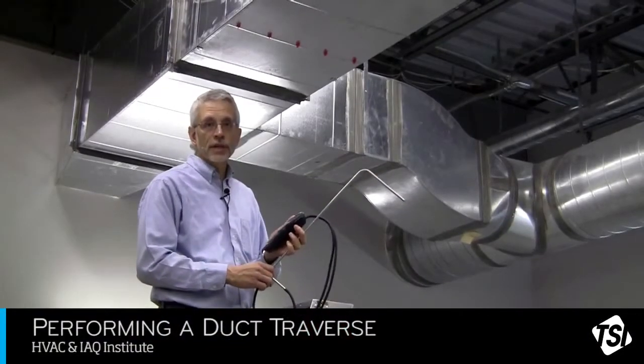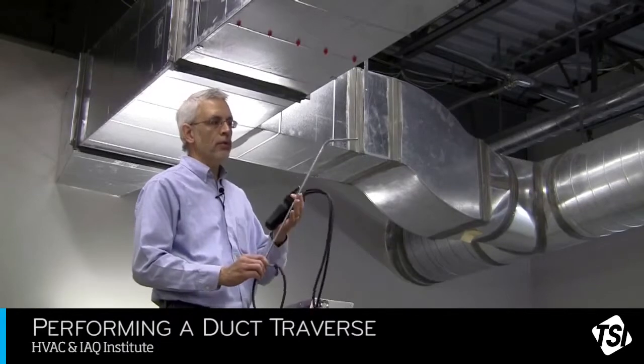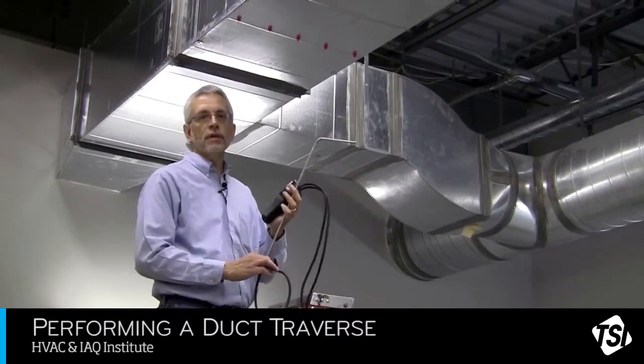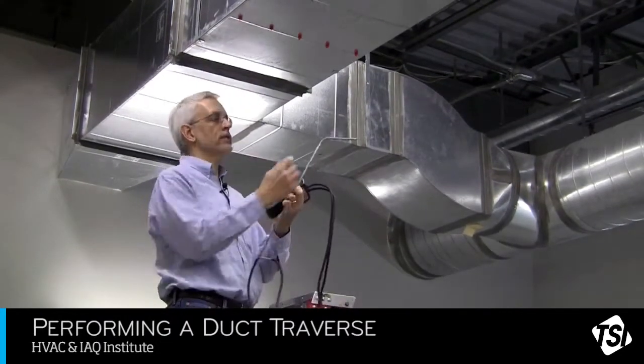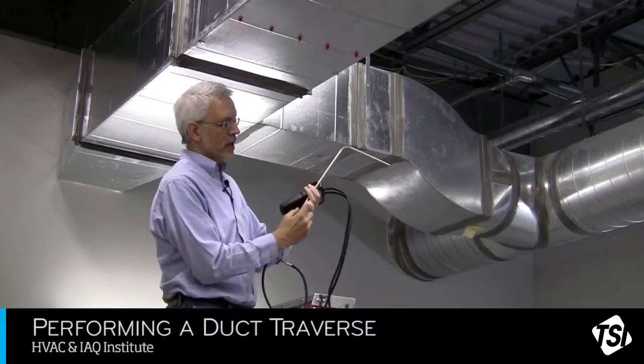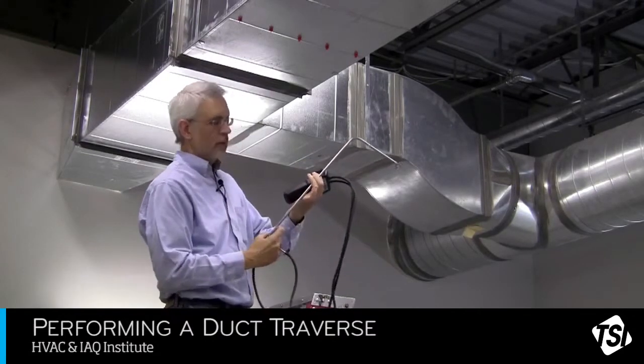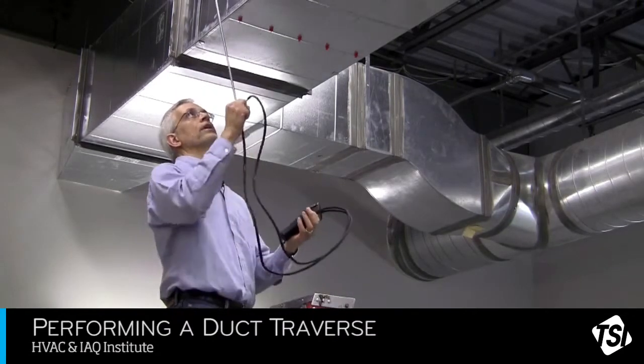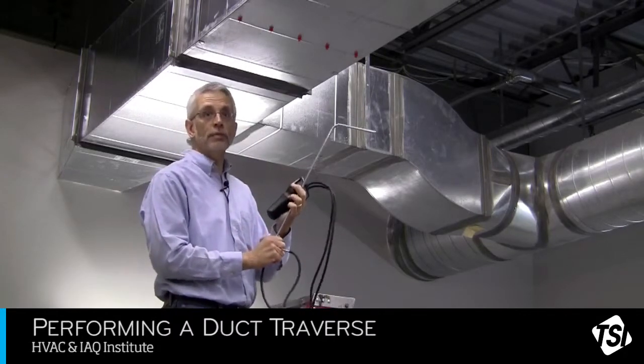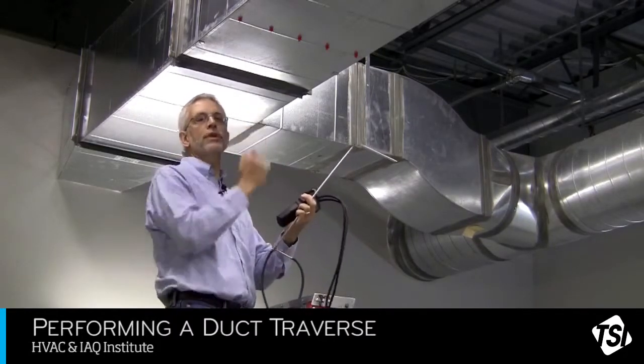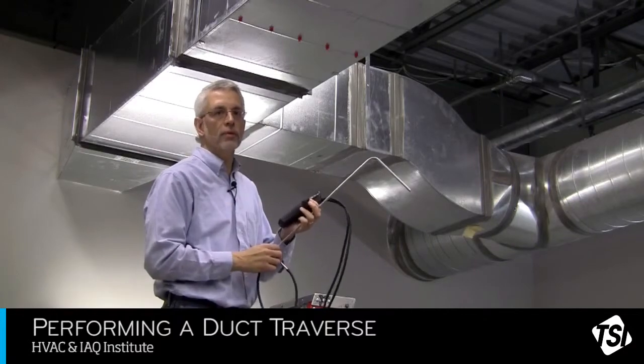Using the AXD 620 and a pitot probe, the technique is the same. I have my duct locations. I have rings on my pitot probe that help me locate the placement within the duct that I need to make my measurements, and I'll proceed to take my 25 duct traverse measurements.